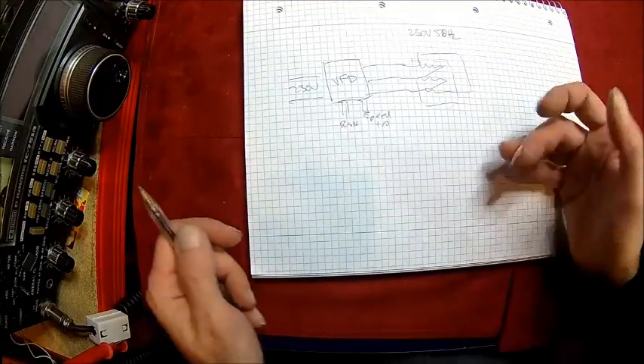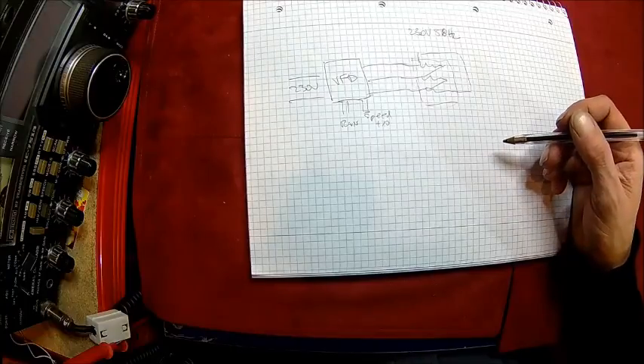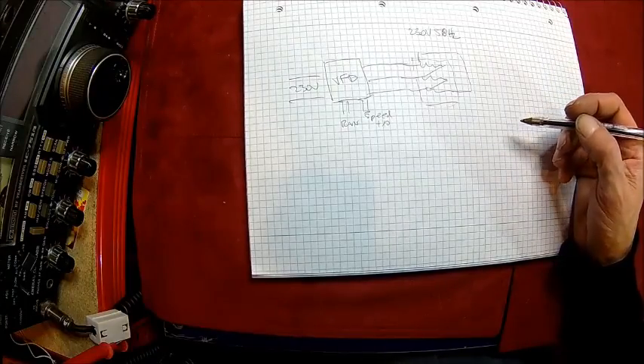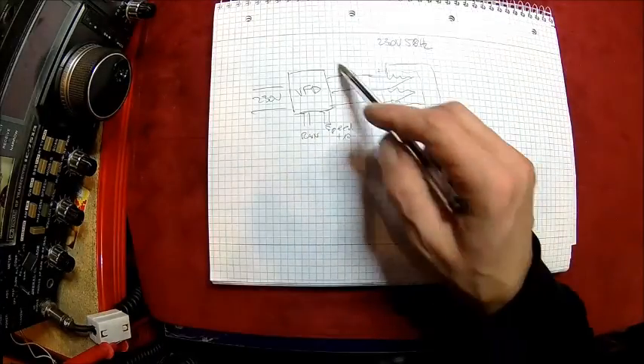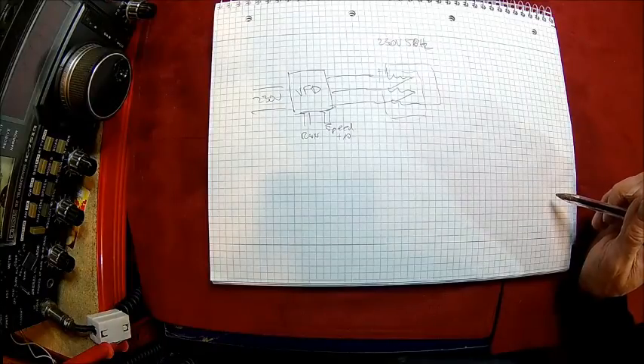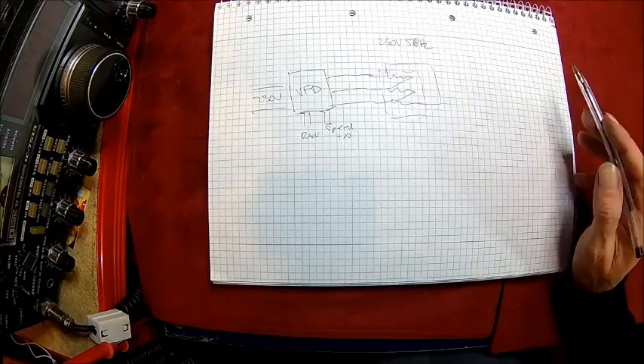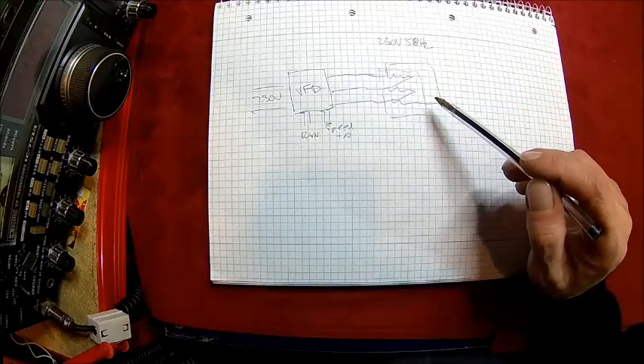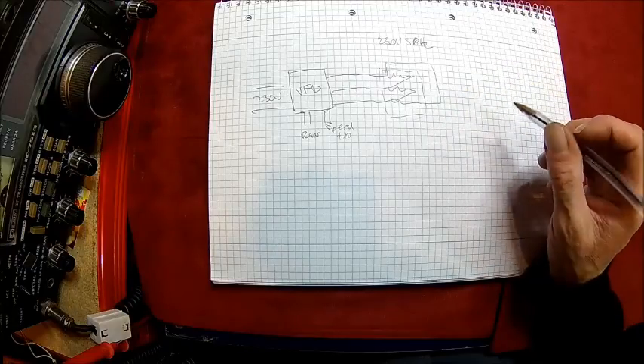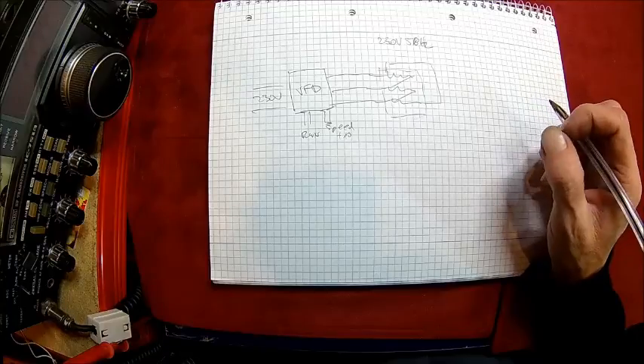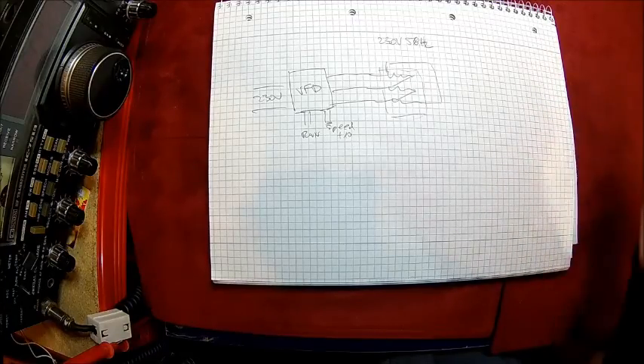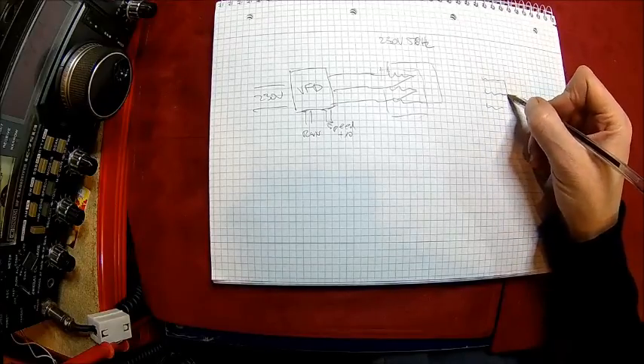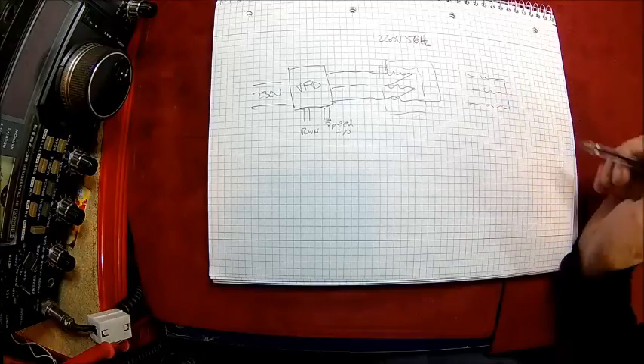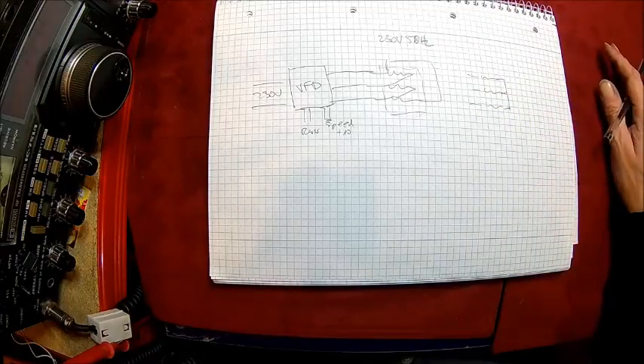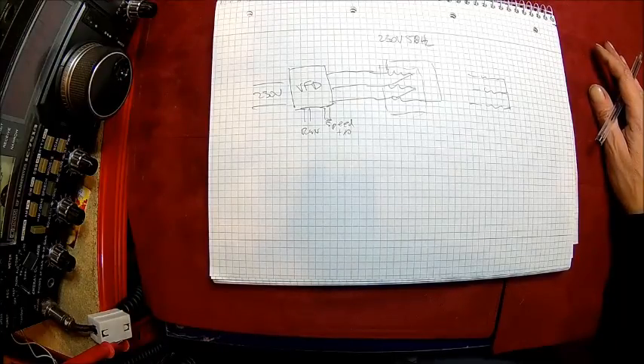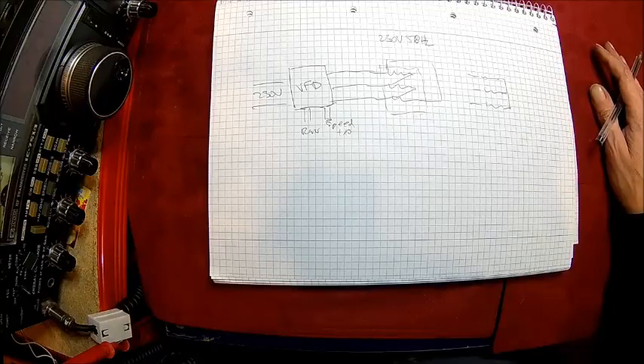Essentially, the trigger of the welder will still run that contactor. You can replace that by a cheaper relay, which I probably will do, because you don't need that big contactor anymore. Simply speaking, the VFD is our power contactor in the welder. Providing you can set your welder to 230 volts in delta. I was lucky that welder is 230 delta 380 star. It's a pretty old machine. So in star it would just look like that. You have your coils and everything is linked together here, and the mains goes here. And that's the high voltage, like a motor. There's no difference between a transformer and a motor. There are differences, but from an electrical point, star delta circuitry, there is absolutely no difference.